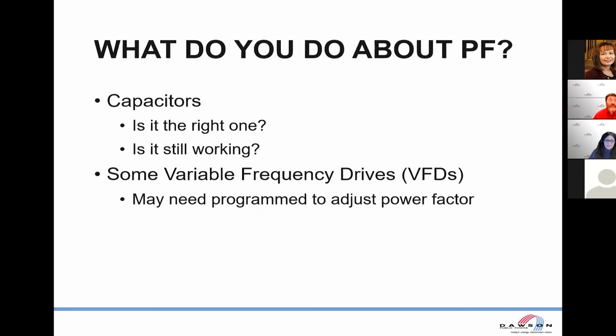All right, well, let's say you've got a variable frequency drive, right? Those don't need capacitors. Why am I below 90% if I have a variable frequency drive? Well, the most likely culprit is that it's not programmed correctly to fix the power factor. So you're going to want to call the manufacturer of the variable frequency drive or the installer to get that corrected.